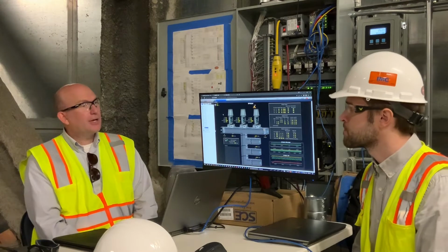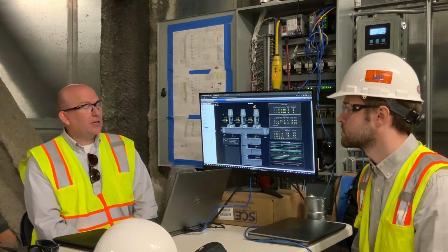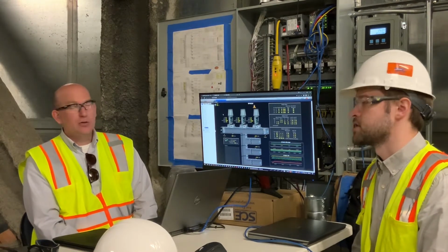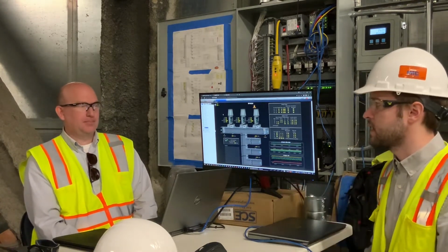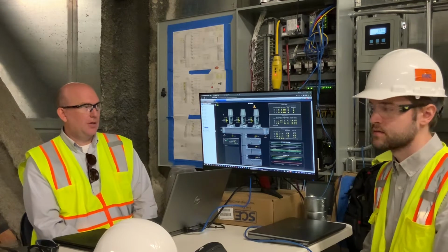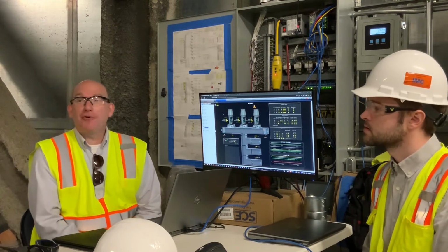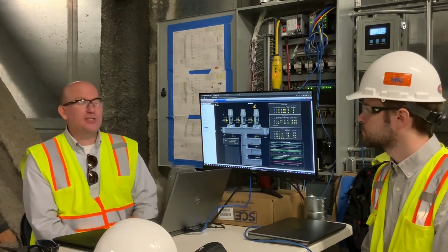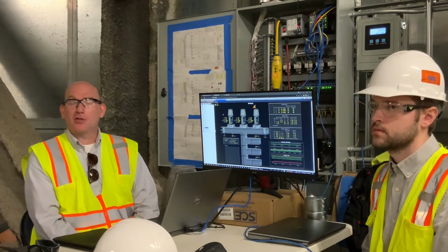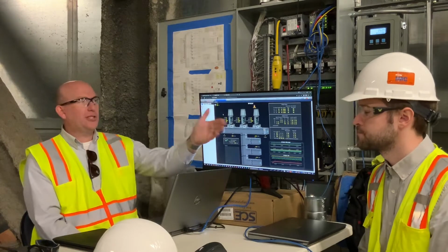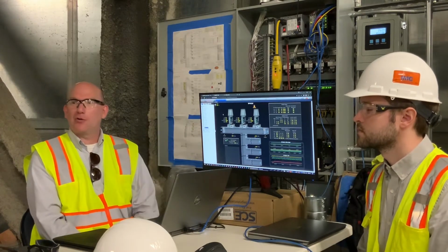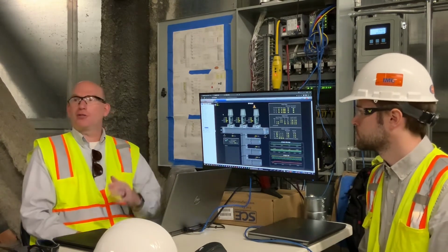Are these configured as lead lag or lead lag standby? Lead lag standby. Okay. There is no scenario where you should see three fans running. You should always have a standby fan just in case one of them fails. If you ever needed it, the logic's in place to run all three at the same time. If we use the same logic for lead lag as we use for lead lag standby, we just flip a bit inside the program to say only ever run two.